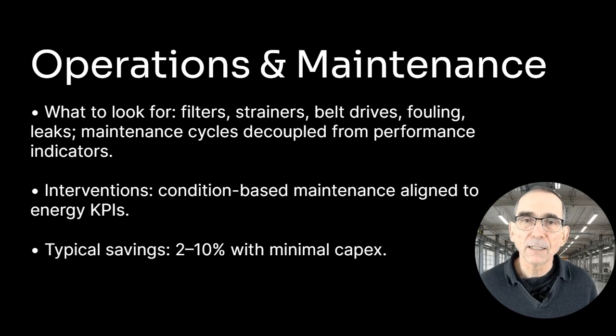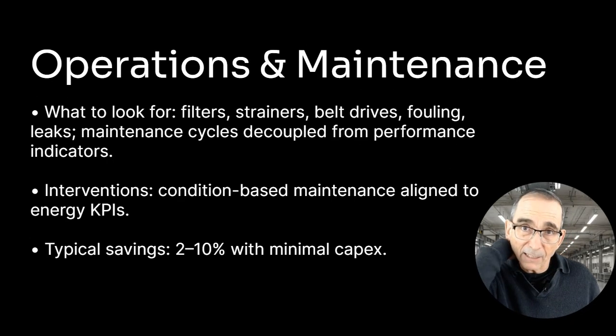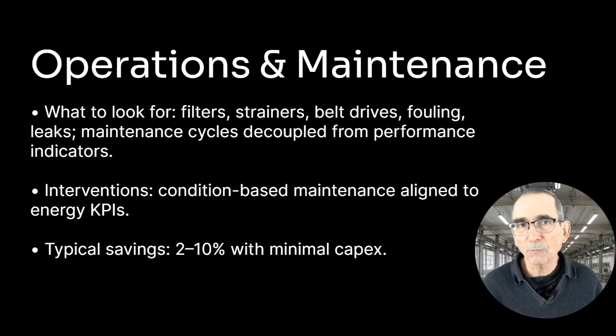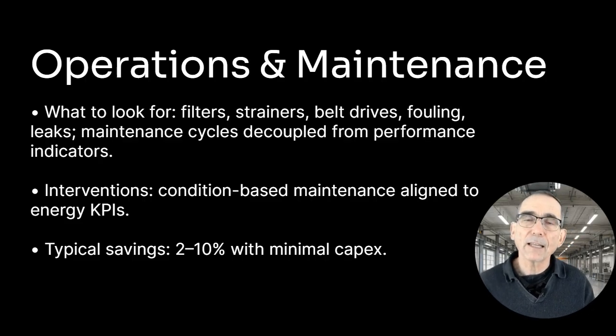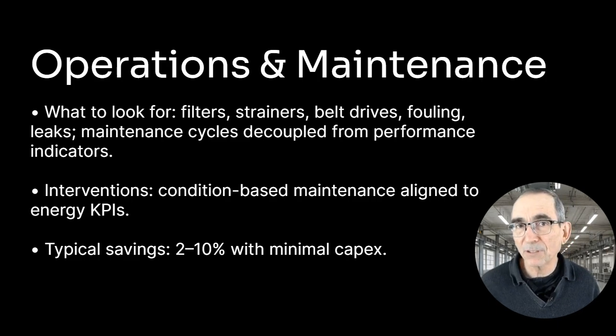Operations and maintenance. Well, this is, again, getting to the nuts and bolts. So you've got filters, you've got steam traps, you've got strainers, you've got belt drives, you've got fouling, you've got leaks, you've got actuators, and then you've got maintenance cycles decoupled from performance indicators. So interventions could be condition-based maintenance aligned to energy KPIs, and instituting some operational KPIs may come back to maintenance, improving maintenance.